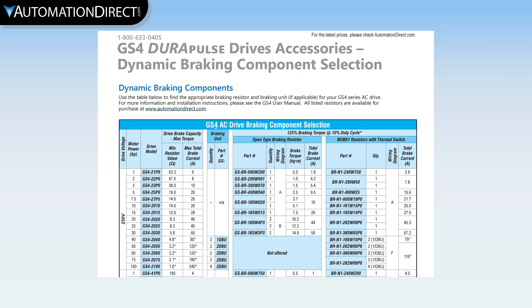Note that a few drives require a dynamic braking unit to add braking resistor. In those cases, the specs or manual will indicate that, and the braking resistors and dynamic braking unit specs will show the required part numbers.